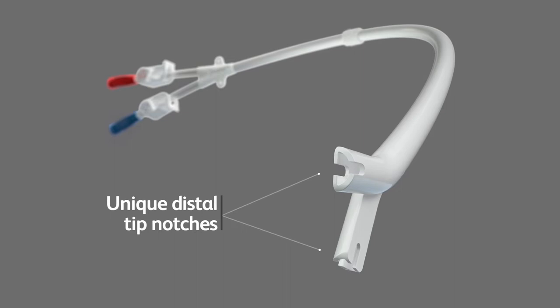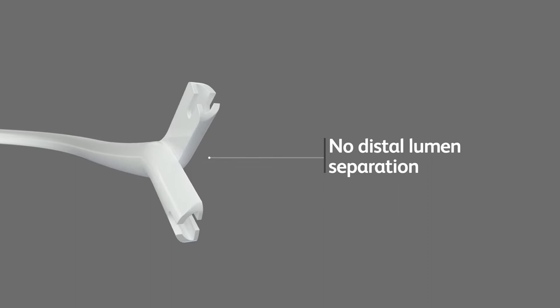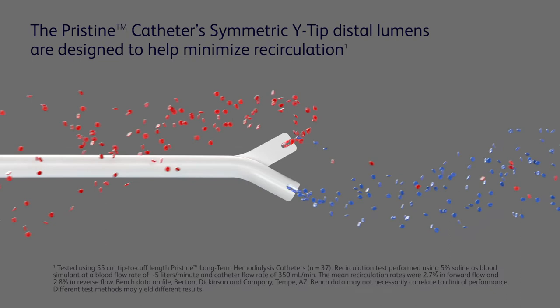The Pristine catheter features a unique Y-tip distal lumen that has no distal lumen separation, eliminating the typical spot where clot formation can occur. In bench testing, the catheter demonstrated high flow rates at low pressures and low recirculation rates in both forward and reverse.